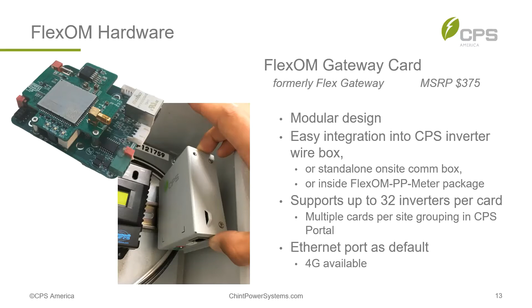Here are further details on the FlexOM Gateway card. As shown previously, the card has a modular design and may be installed in the inverter wire box or inside a DAS enclosure using the supplied optional metallic DIN rail mount enclosure. It may also be mounted inside the FlexOM PP meter enclosure, which we'll cover in a few slides. The card supports up to 32 inverters connected on the Modbus RS-485, and is available with an optional 4G modem integrated on the card when purchased with the performance package. This base FlexOM card, without the PP or performance package, does not include customer access to the FlexOM portal.